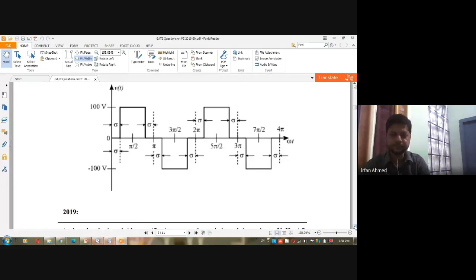Very simple question. The only thing is you should know that for a 6-pulse bridge rectifier, the AC current is a quasi square wave, so the third harmonic is 0, the lowest harmonic is the fifth. After the fifth harmonic, you will have the 7th harmonic, then 11th, 13th, and so on.